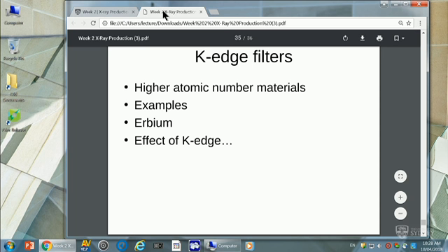Okay. Now, the thing that you should notice here, which is completely different from the non-selective filters, is that you now have got rid of all this soft radiation, not all of it, but a lot of this soft radiation, but you've also now got rid of a lot of the high energetic radiation. What does high energetic radiation do to your X-ray image? Reduces contrast. Suddenly we've got a filter that not only reduces dose and reduces the soft radiation, but it enhances quality.